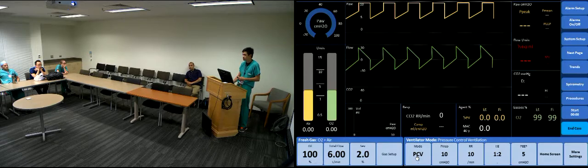So you will see the respiratory therapists switch very commonly in all settings. If they're not doing well in the volume control, their go-to becomes pressure control before they start calling and relaying up the ladder that this person's having a problem with gas exchange. But the decelerated waveform is thought to improve gas exchange. The problem is that your compliance changes throughout time, so you can't guarantee the volume you get. So you need pretty strict vigilance if you're in someone on that mode. And then again, with control mode, mandatory breath. Try to breathe, the machine's not going to help you. You're going to be fighting against the machine, okay?